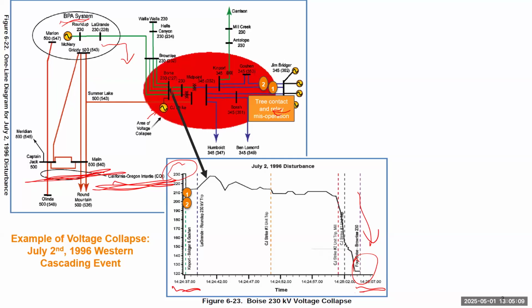The first event is just a short circuit due to some tree contact and also some relay misoperation. That shouldn't trip those 2 main transmission lines sending power from the power plant to the load center. But there are 3 lines, and 2 of them are open. So the power from this power plant to the load center was largely impacted. Then it calls a special protection system, which tries to protect the generators. So that power plant lost 1 gigawatt of generation. That largely increased the line flow from the north region, and that made that line almost overloaded.